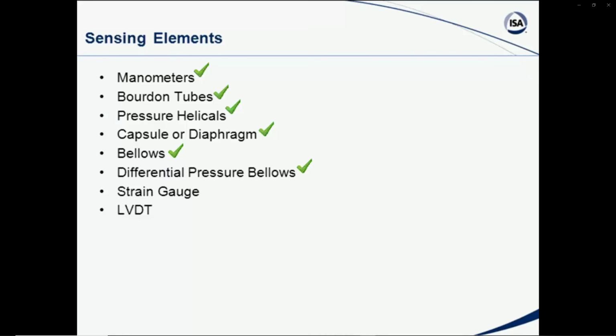We'll also use diaphragms, capsule type, for our primary measurement sensing devices for the transmitters. We use a lot of those, and on those, as those diaphragms have small movements, we will be using either some sort of a strain gauge or a variable capacitor, and as that pressure varies some, it would change the output. And then some devices actually use a linear variable differential transformer, whereas a core is moved through a magnetic field. It changes the coupling on the particular transformer, and we get different outputs. So there's a lot of different devices. These are covered in books, and everything that we talk about, there's books written about them basically.